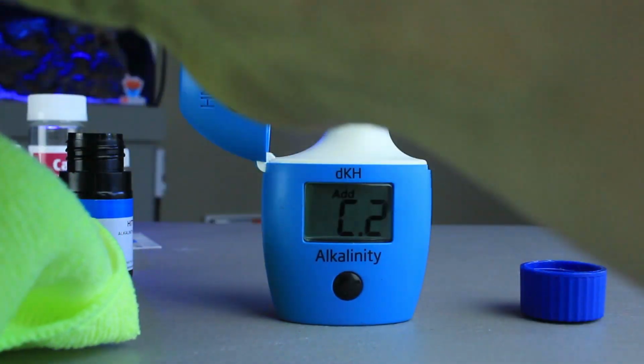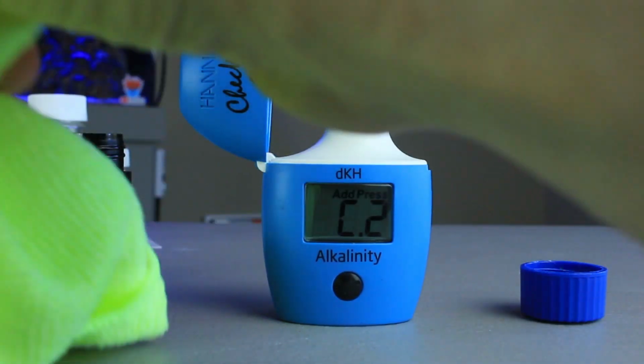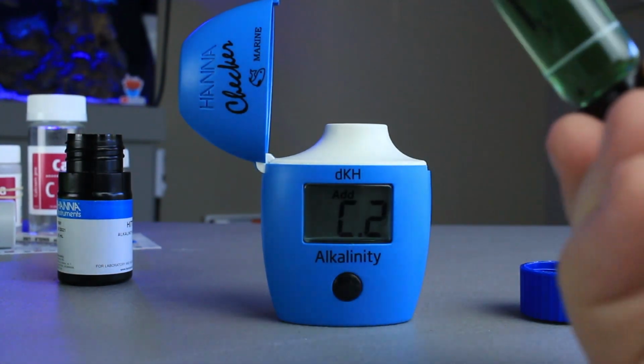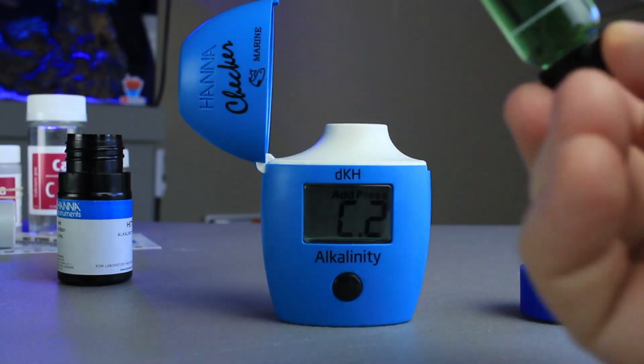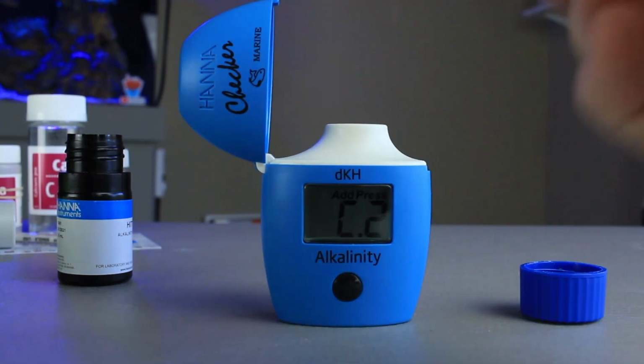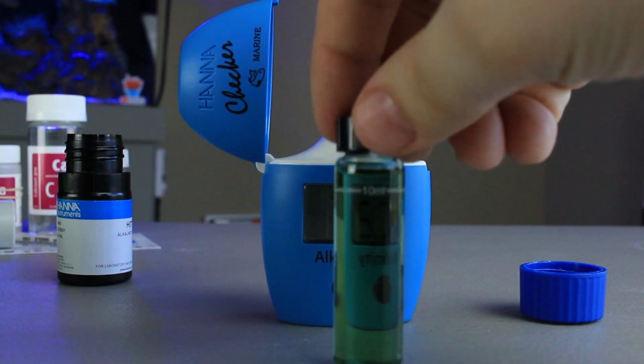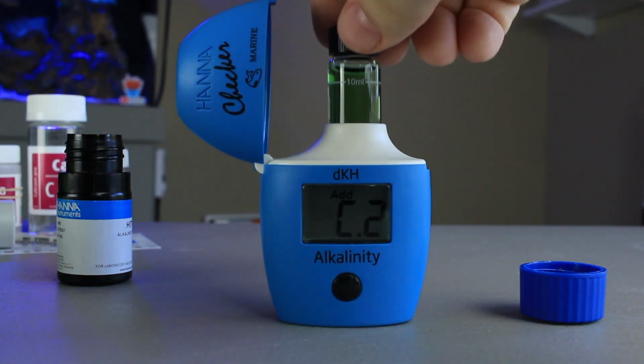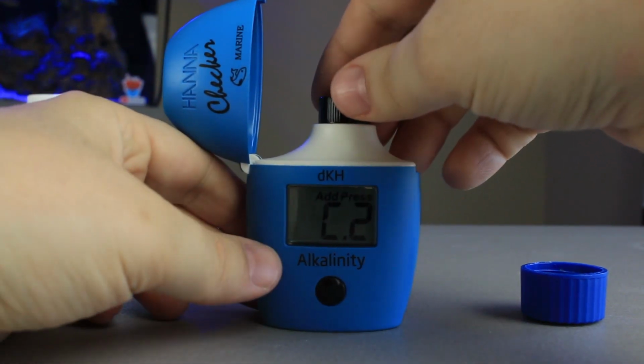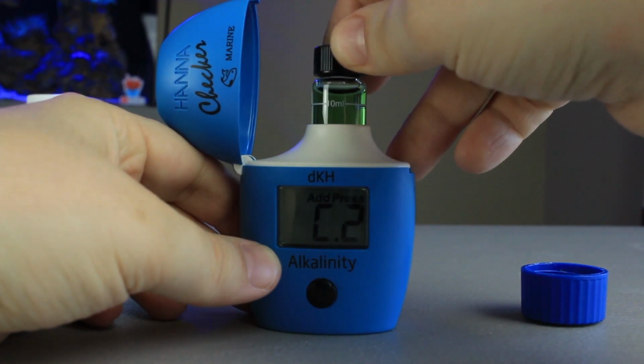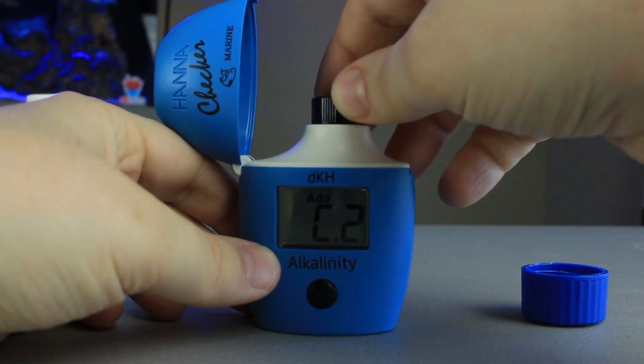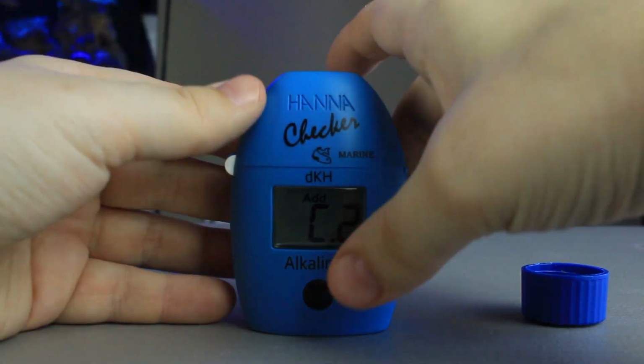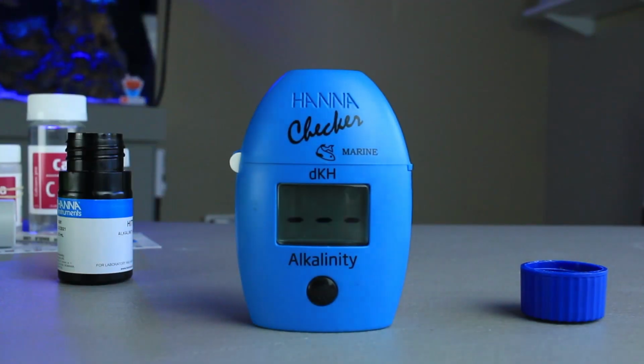Let's put our cap back on so we don't spill it. And I'm going to go ahead and clean it one more time with the microfiber cloth. And I'm just going to invert it a few times just to make sure all the reagent is mixed up with the sample water. I like to use the 10 ml line where it's marked to face the front, so I know it's always getting the same exact reading. Simply close it up and we should get our result.